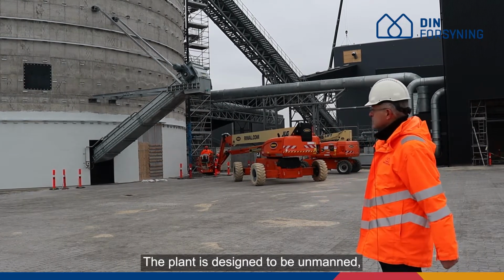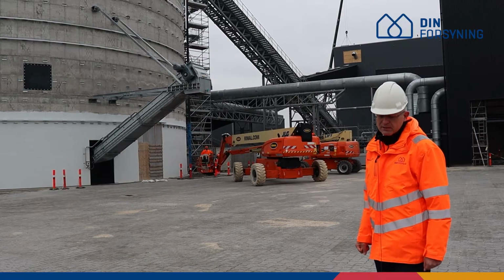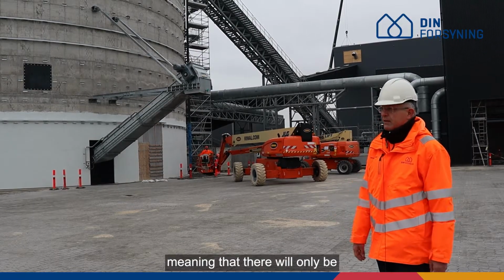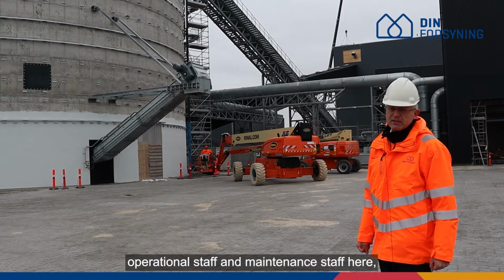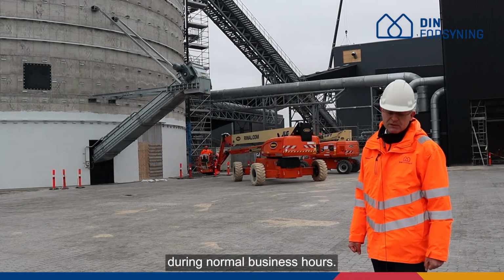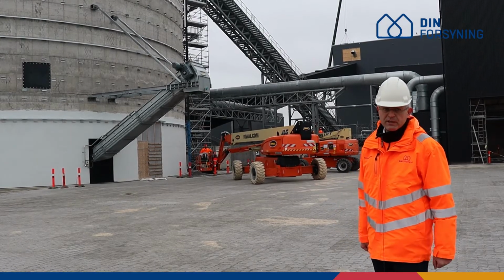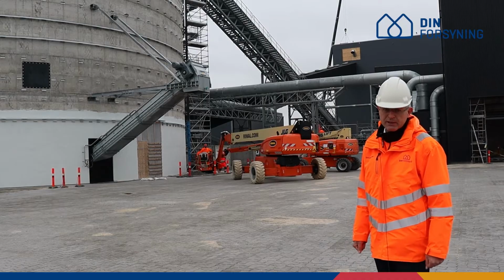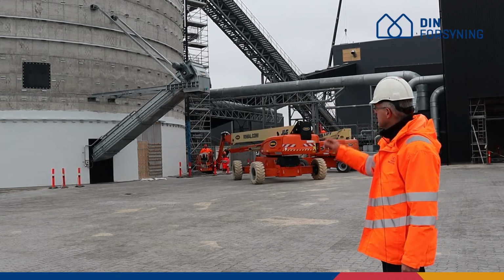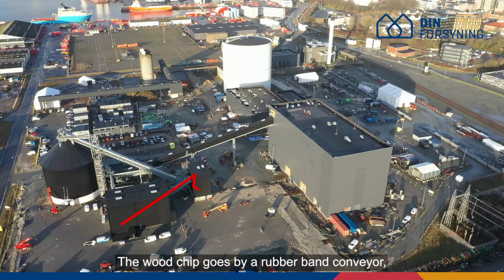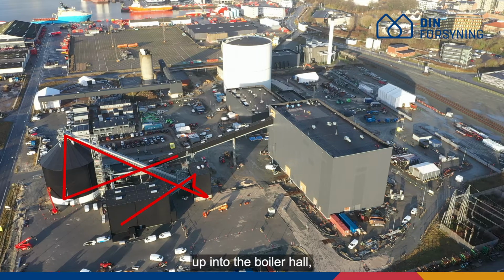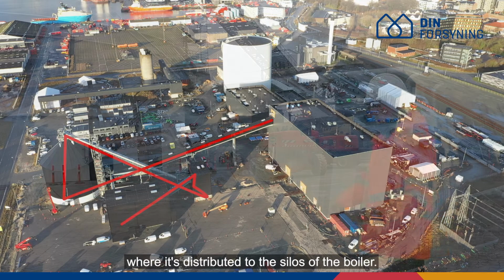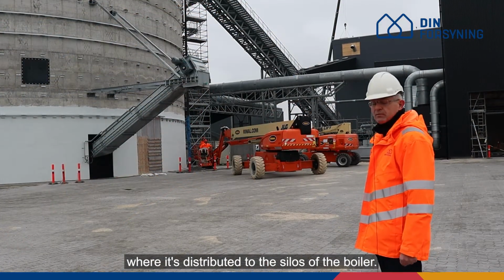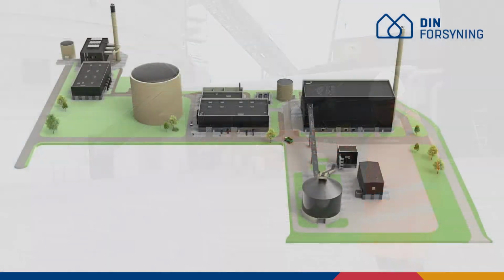The plant is designed to be unmanned, meaning that there will only be operational staff and maintenance staff here during normal business hours. So weekends, holidays, whatever, it's not planned for anybody to be here. It will run automatically. That's the reason for the size. And the wood chip goes by a rubber band conveyor up into the boiler hall, where it is distributed to the day silos of the boiler.